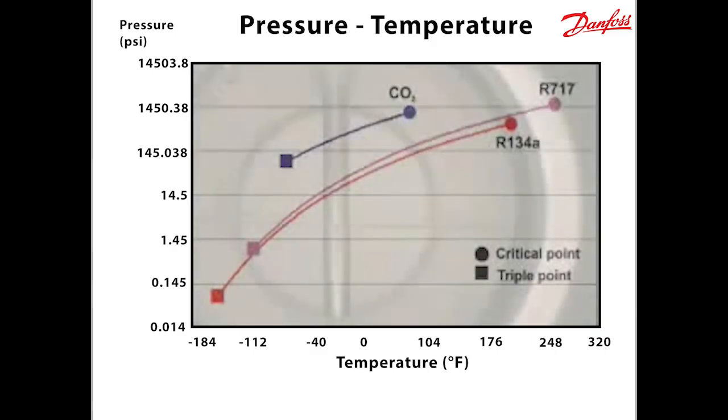Compared to commonly used refrigerants, R134A and R717, CO2 has some unique characteristics. It operates at a much higher pressure, but across a narrower temperature range than R134A and R717. The pressure at the triple point is high, and the temperature at the critical point is low.